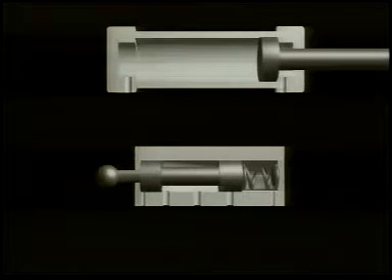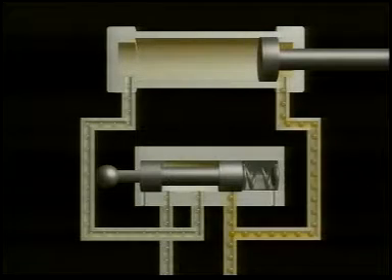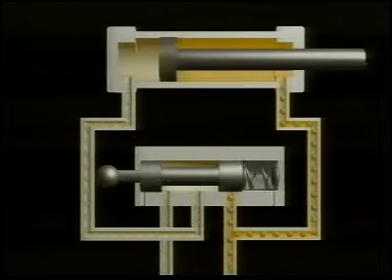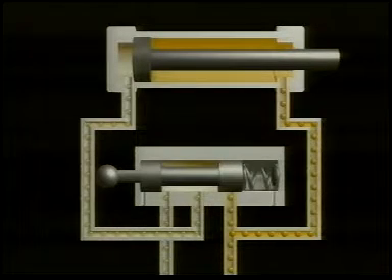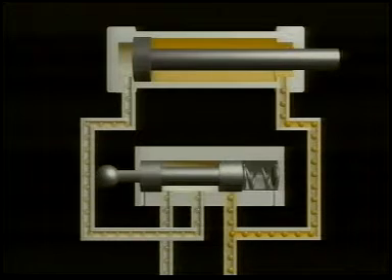To make advance and retraction the same, a 3-2-way valve can be used to set up a differential circuit. The line to the piston rod chamber is not connected to the valve, as is normally the case, but is connected to the pressure line between the pump and valve. As we can see, this means that the rod side is always under full system pressure.